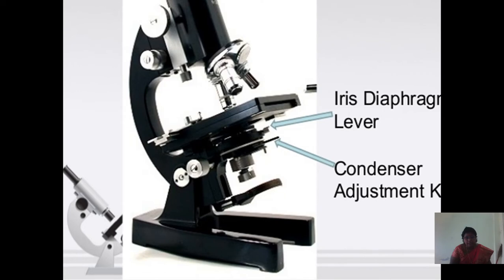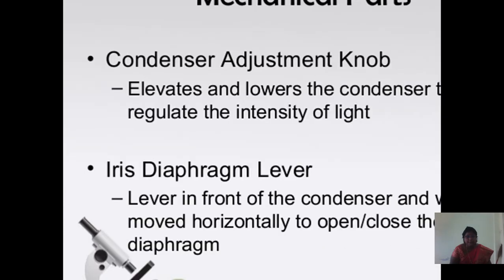The iris diaphragm lever and condenser adjustment are also mechanical parts. The condenser adjustment knob elevates and lowers the condenser to regulate the intensity of light. The iris diaphragm lever is positioned in front of the condenser and is moved horizontally to open or close the diaphragm.